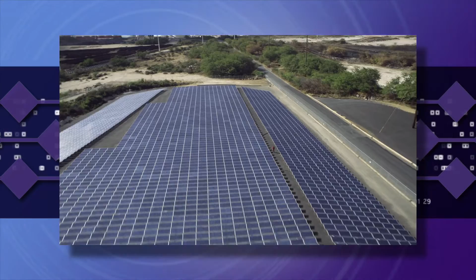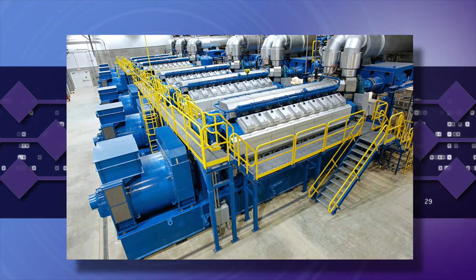Let's say we have 300, 400 megawatts of solar on the system and the clouds are rolling over and we start having what is effectively a loss of generation. The Schofield generating station will be able to start and be online in well under 10 minutes and could actually be at full load in that time. Therefore, the Schofield generating station is able to counter the effects of the variable generation.